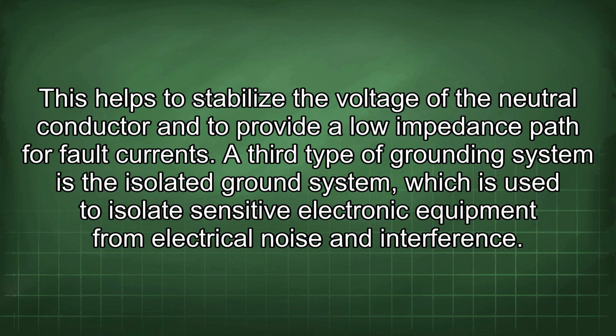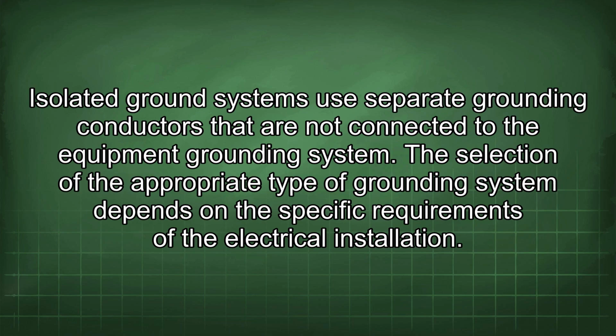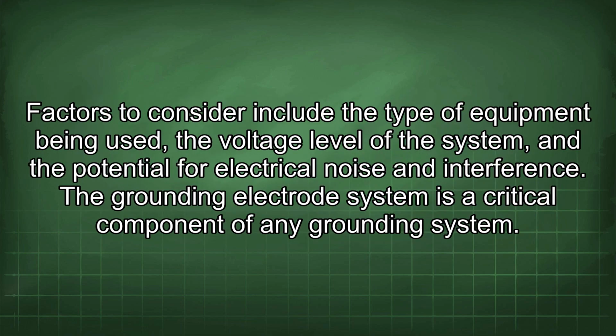A third type of grounding system is the isolated ground system, which is used to isolate sensitive electronic equipment from electrical noise and interference. Isolated ground systems use separate grounding conductors that are not connected to the equipment grounding system. The selection of the appropriate type of grounding system depends on the specific requirements of the electrical installation. Factors to consider include the type of equipment being used, the voltage level of the system, and the potential for electrical noise and interference.